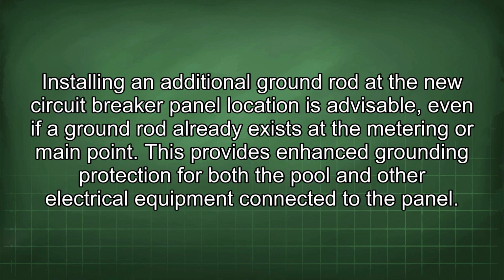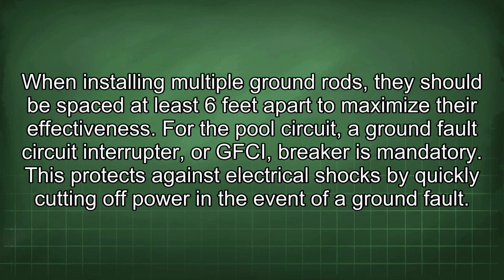Reducing the distance helps minimize voltage drop, ensuring the electrical panel operates efficiently and reliably. Installing an additional ground rod at the new circuit breaker panel location is advisable, even if a ground rod already exists at the metering or main point. This provides enhanced grounding protection for both the pool and other electrical equipment connected to the panel. When installing multiple ground rods, they should be spaced at least 6 feet apart to maximize their effectiveness.